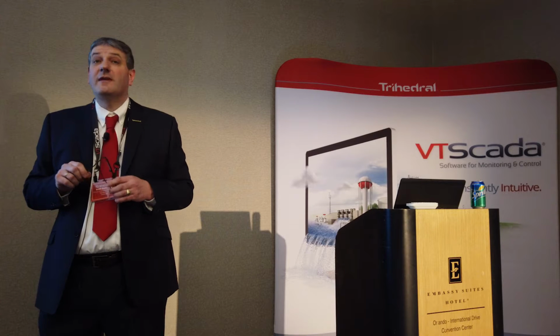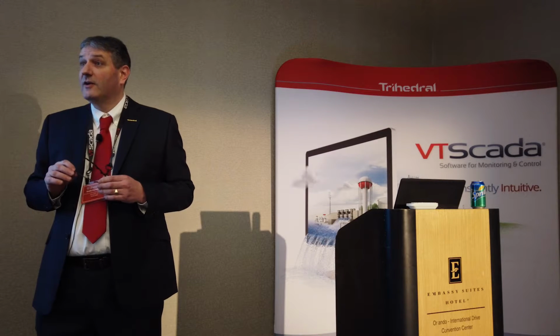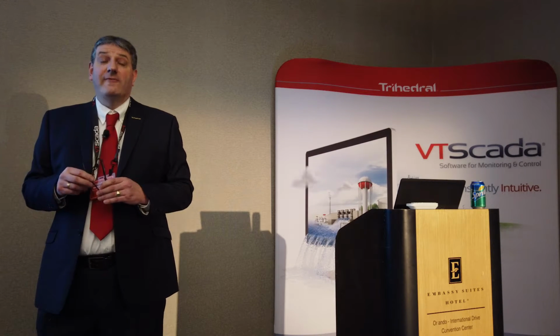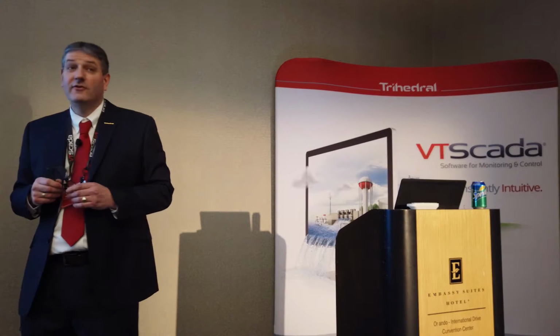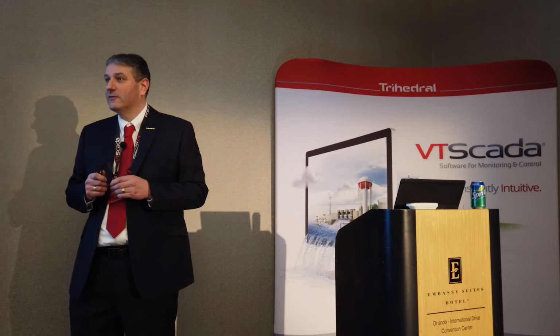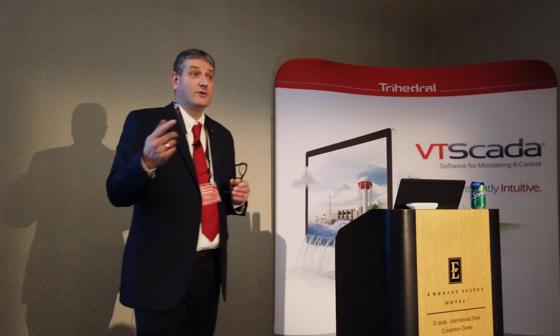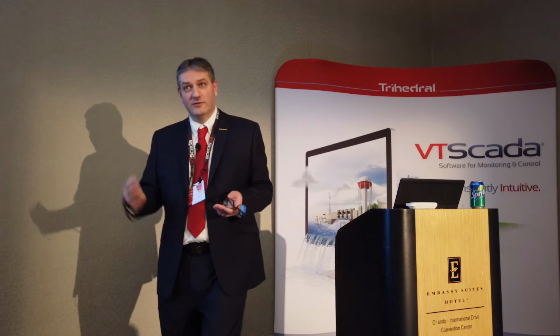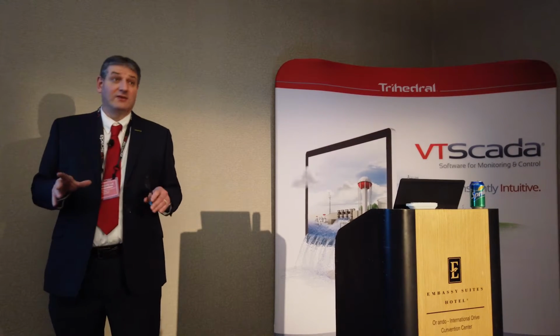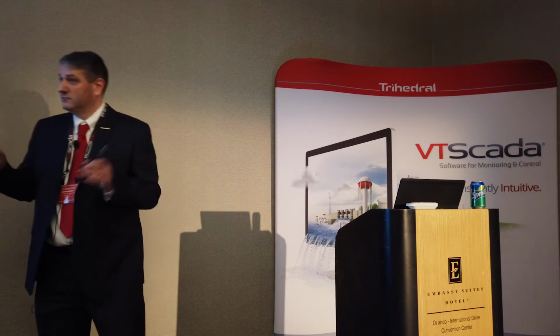If you happen to be debugging on the application thread, so that's maybe in a driver or in a data point, everything in the application thread will stop. That is all of your drivers, your inter-machine communications with other servers, or if you've got a watchdog, for example, we've got systems with hardware watchdogs, it will stop updating the hardware watchdog. It will think the system has frozen solid and do whatever actions, usually reboot the computer. So you have to be very, very careful placing a breakpoint, especially on a production system. So, warning.